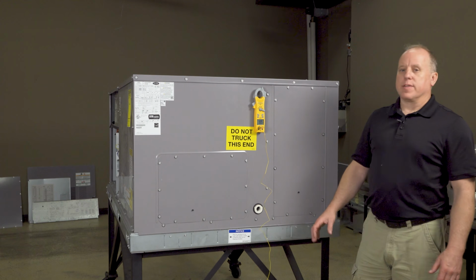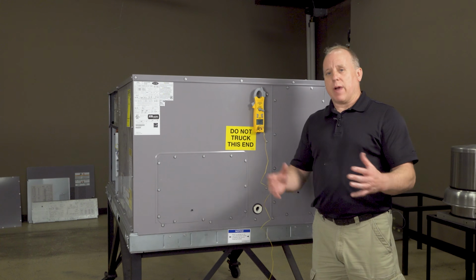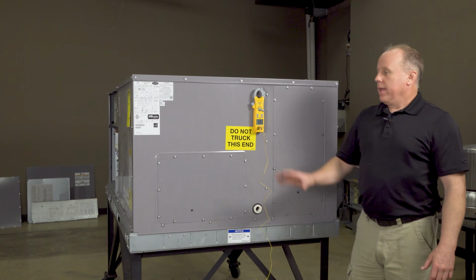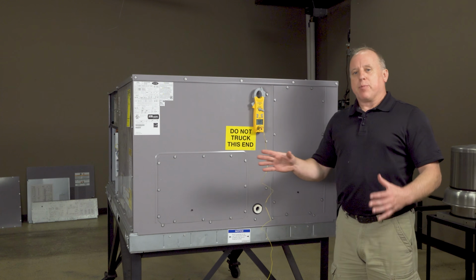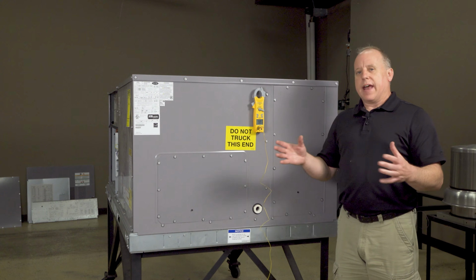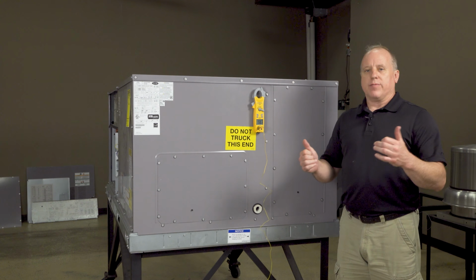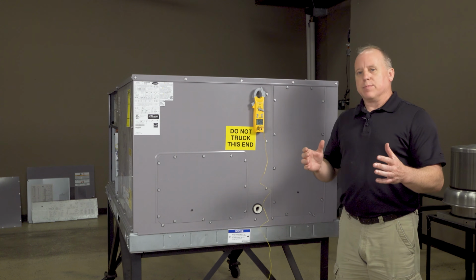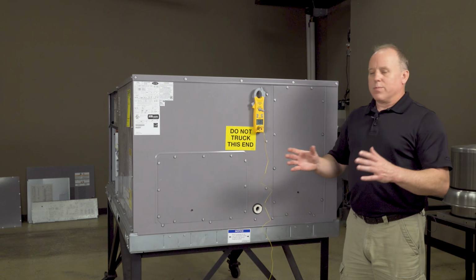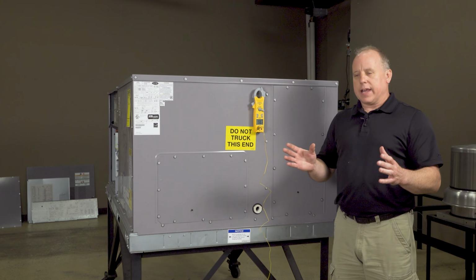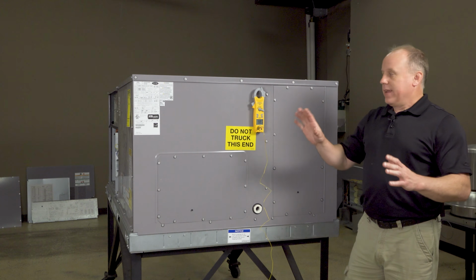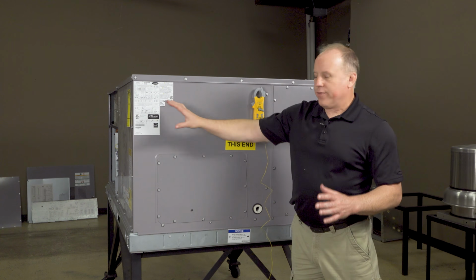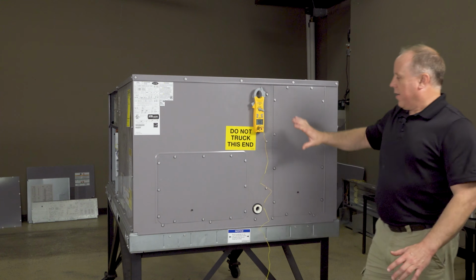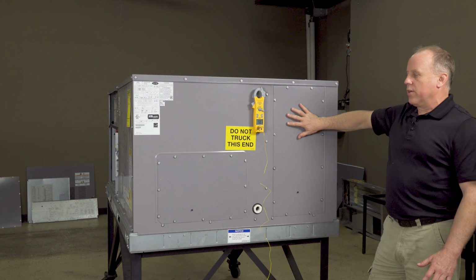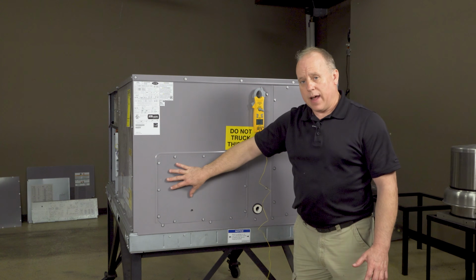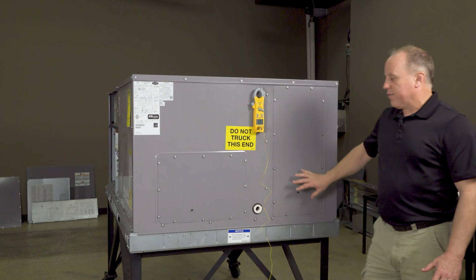Okay, now we're going to go over temperature drops, possibly temperature rise, depending on what we're talking about. Referencing the temperature the unit's operating at, putting out, is going to tell us again how it's operating. It'll indicate if we have dirty coils, if we're having a problem somewhere with the unit. So quick, relatively simple to check. If we're out on the unit outside, on the roof side of the building, right here, this side of the unit's going to be our return. This is going to be our supply. So we could access directly from here.